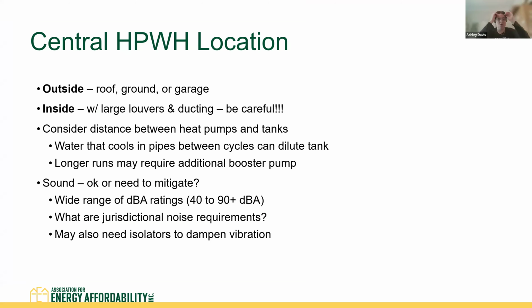So you also have to think about where the heat pump units themselves are going to be located. Most often we see these outside, on the roof, on the ground, or in a garage. Occasionally we see them inside, but circulation was important for a small tank type heat pump water heater, and it's going to be even more important for a commercial sized heat pump water heater. So if you are going to install them inside, make sure you're connecting with the manufacturer and following their guidance about proper ventilation and air circulation.